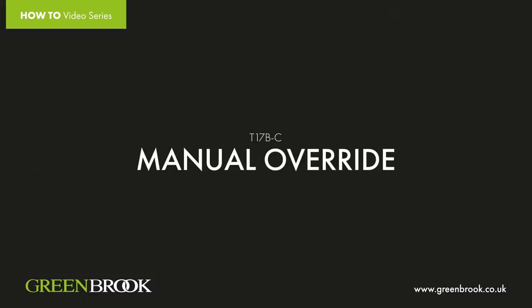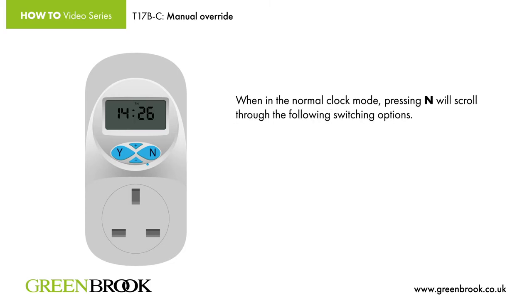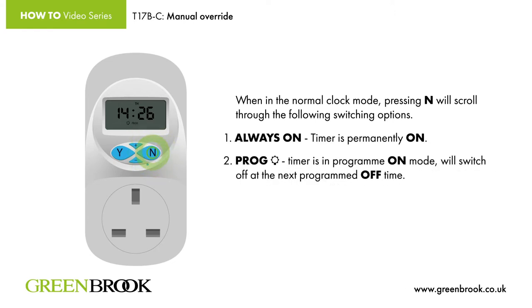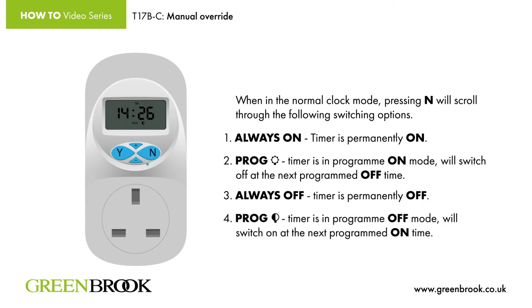Manual override. When in the normal clock mode, pressing N will scroll through the following switching options. 1: Always on — timer is permanently on. 2: Prog — timer is in program on mode and will switch off at the next programmed off time. 3: Always off — timer is permanently off. 4: Prog — timer is in program off mode and will switch on at the next programmed on time.